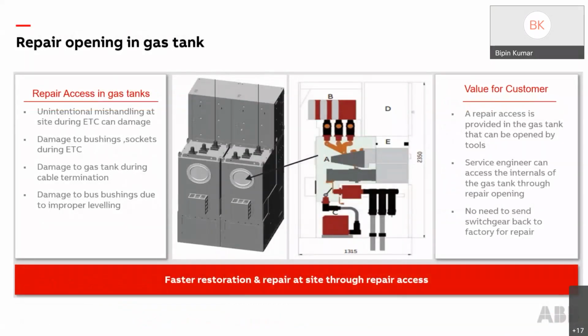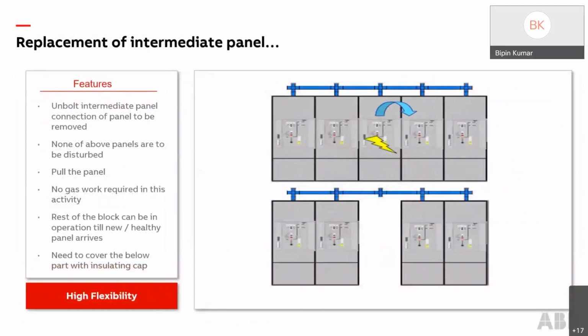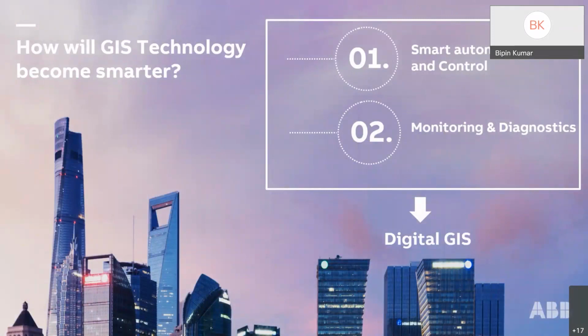We also give, because GIS is a maintenance free product, but then you can also have a repair opening in case something happens, because products are always designed to handle the worst circumstances. But then yes, as a design feature, this is also available. Once we have taken the bus outside the switchgear, then we can take any intermediate panel. Now I come to the sensor topic, as it was also touched upon, how we are bringing the sensor technology and what the future is going to look like.